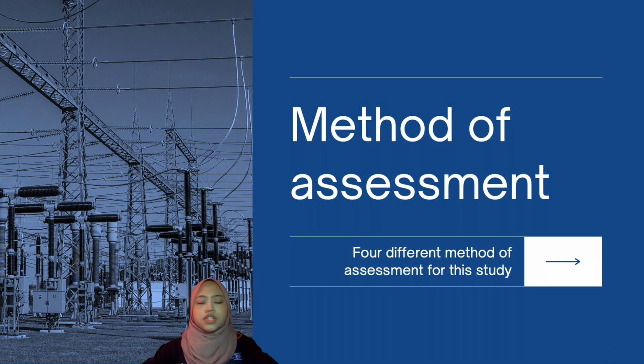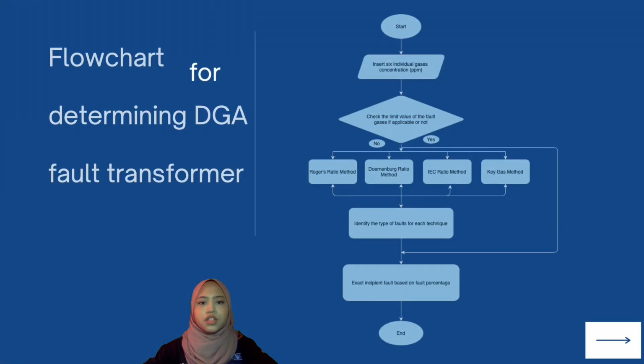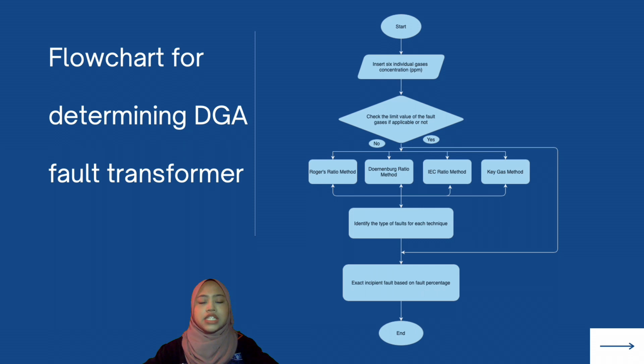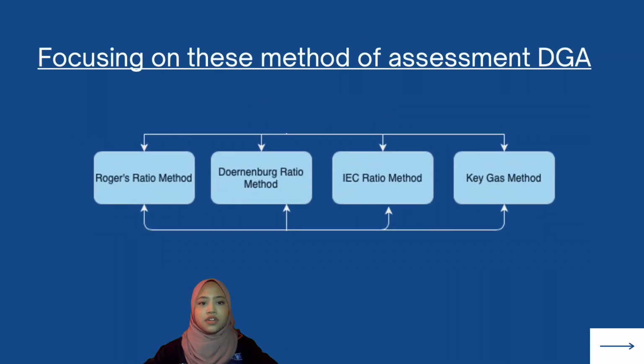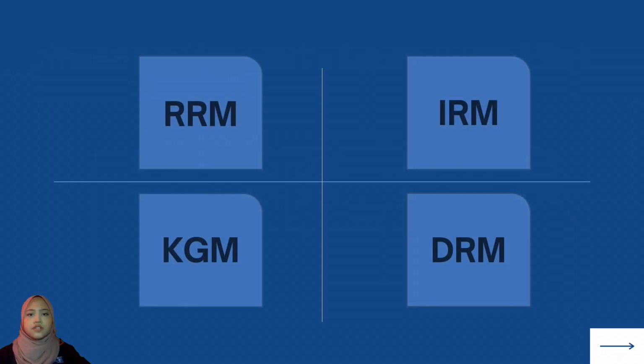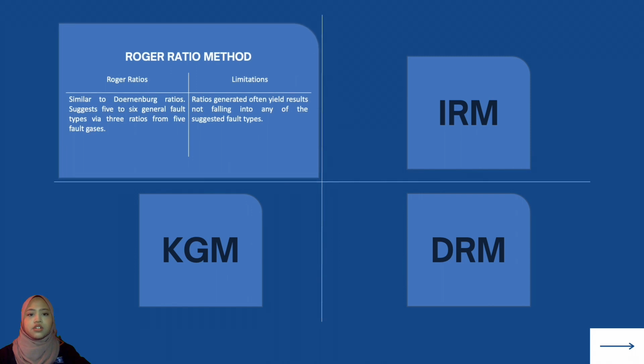Next is the method of assessments. This is the flowchart for determining DGA faults in transformers. However, this study focuses more on these DGA methods of assessment. First is the Roger ratio method. The Roger ratio method is similar to Doernenburg ratios, suggesting 5 to 6 general fault types via 3 ratios from 5 fault gases. The limitation is that the ratios generated often yield results not falling into any of their suggested fault types.